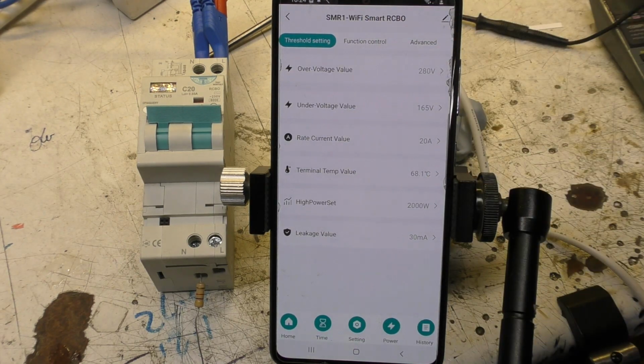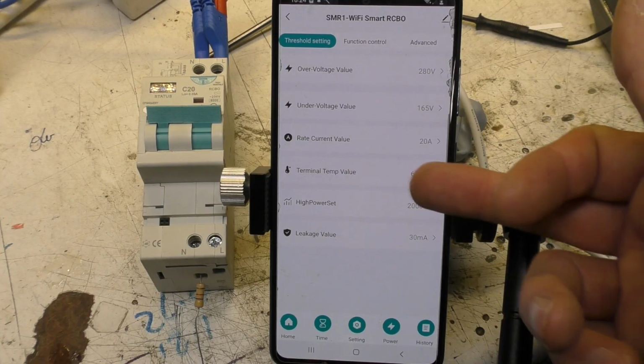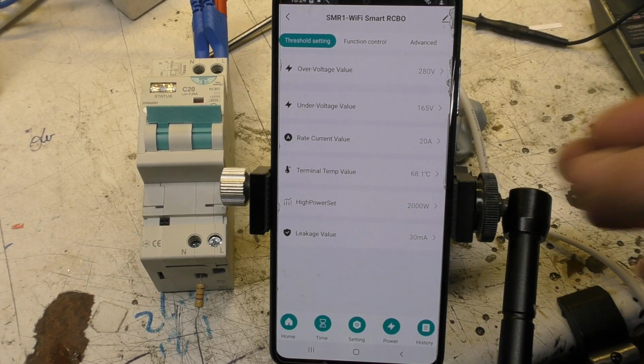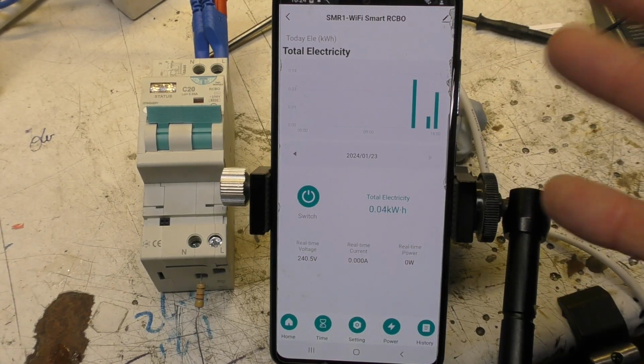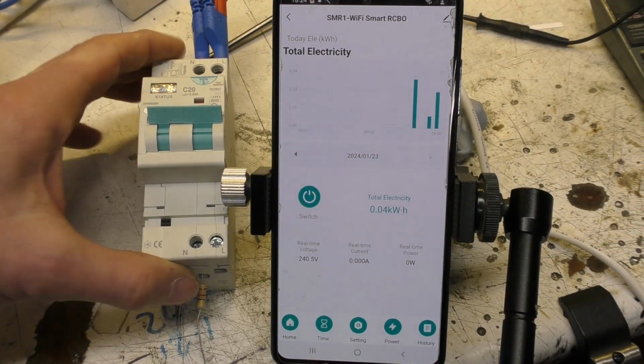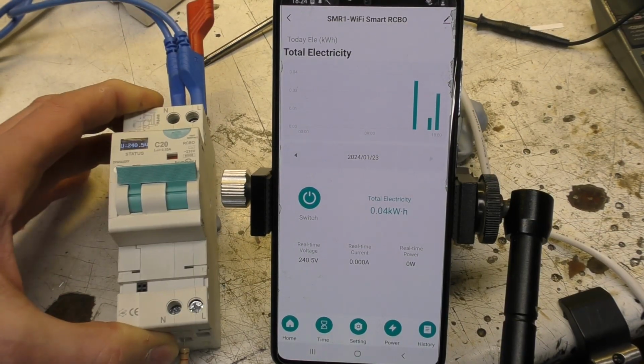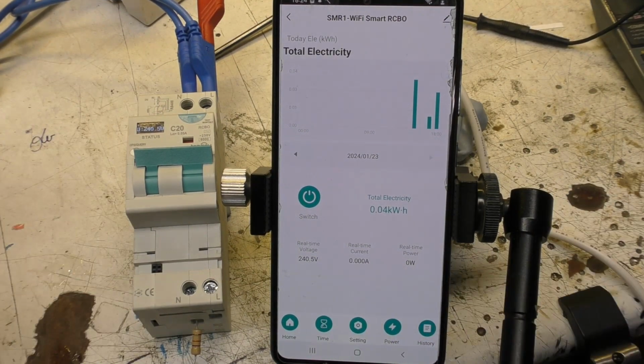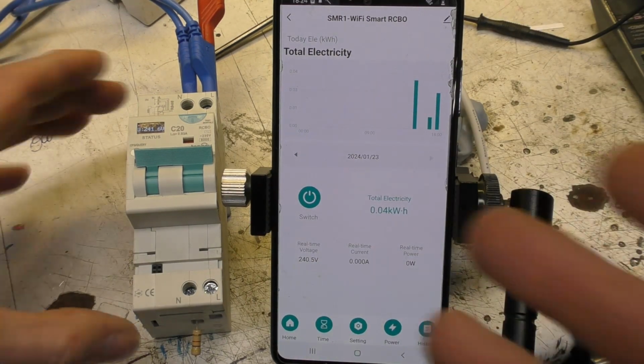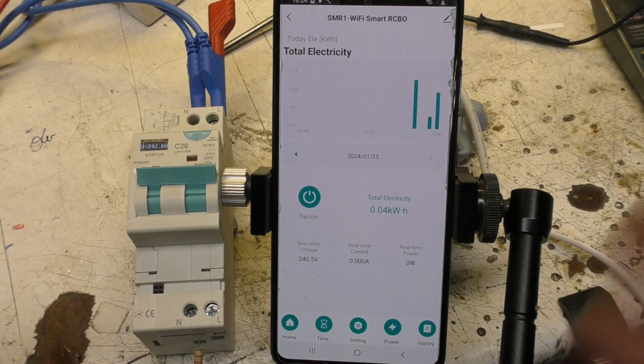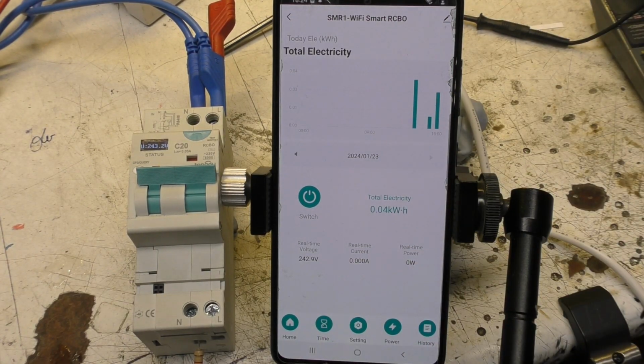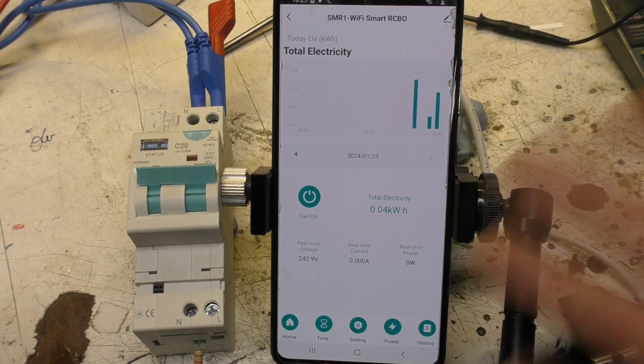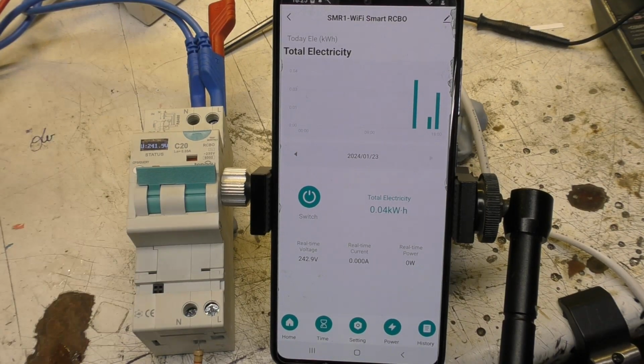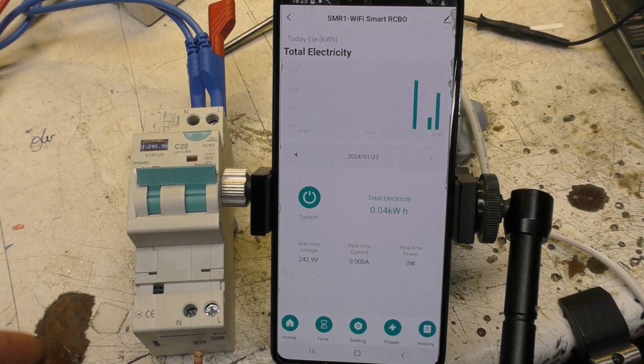Settings: we've got over voltage, under voltage, trip current, and again terminal temperature value, which could be useful to detect overheating, and power limiting. So to summarise, all these are potentially useful functions, but not in a device that looks like a circuit breaker. Even though this is beautifully built, with superb construction quality, the very fact that a device that looks like a circuit breaker can disable those functions means it is a very dangerous, potentially dangerous product, because someone could come along to a board, not knowing exactly what to expect, expecting to find normal circuit breakers, for example, switch it off, go to work on a circuit, and then find it just switches itself back on again, which is potentially lethal.